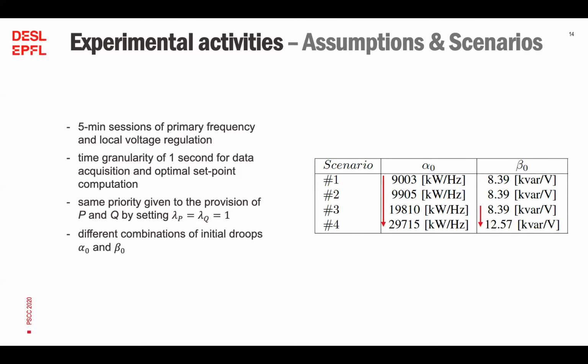So finally, going to some results. As mentioned before, we performed some experiments at our facilities at the EPFL campus. The real-time control has been run for dedicated control tests with a time granularity of 1 second for phasor measurement data acquisition and optimal set point computation. The communication between the battery energy storage system and the proposed controller has been established with Modbus TCP, and all the computation has been carried out in a MATLAB environment.